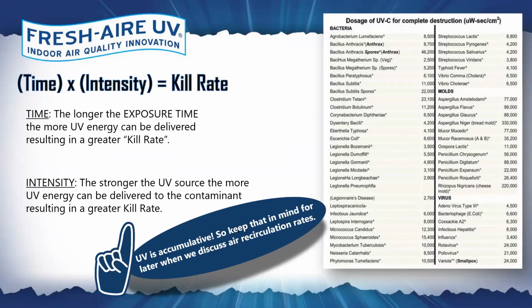But what's lucky for ultraviolet is typically in the world of microorganisms, when we're talking about airstream disinfection, we're typically looking at bacteria and viruses. And in the grand scheme of things, bacteria and viruses are pretty weak when it comes to ultraviolet. And when we look at molds and funguses that are more resistant to ultraviolet, requiring those high dosage requirements, well, they're pretty much not necessarily airborne. They're thriving on surfaces inside the air handling unit. So when we want to address Aspergillus niger, for example, we have a UV light mounted in the air handling unit, disinfecting the drain pan and the coil surfaces.